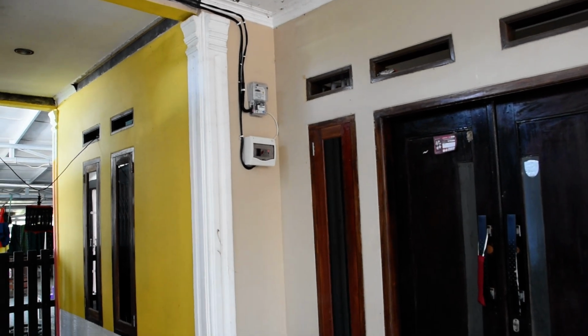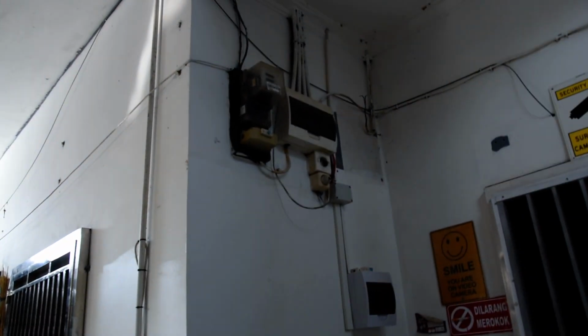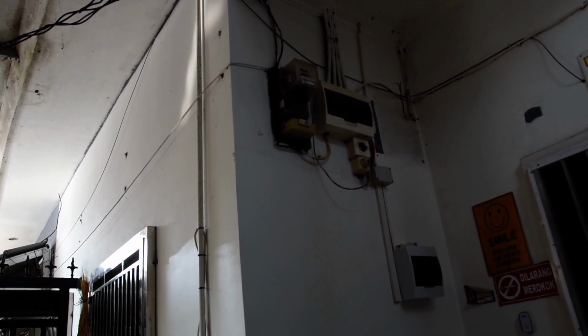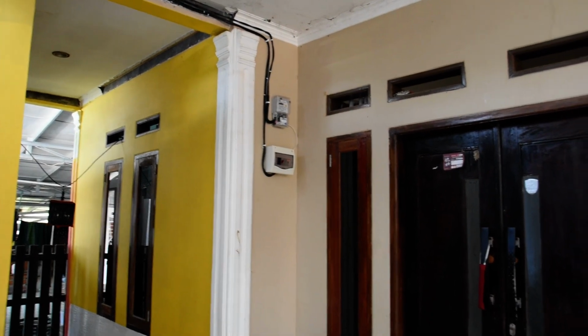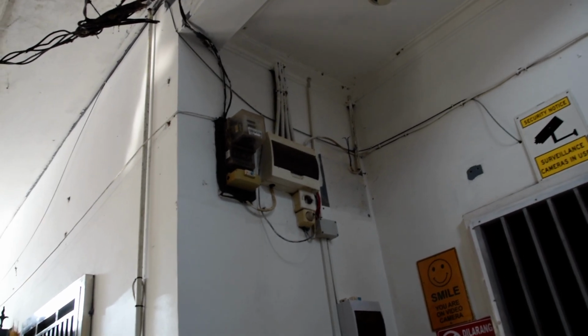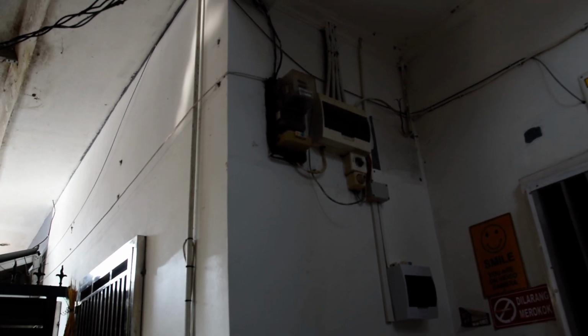So a major driver in getting Lizu's house on the Publik Listrik Network, with just backup from the off-grid network, was to reduce the overnight load on this old switchboard with the house, thinking that might reduce the chances of tripping that breaker. The last event where it tripped 4 times overnight was after we got that new meter over here at Lizu's house. So I really don't understand. At this point, the only things on that old switchboard are the lights, the 4 of the air conditioners along the south side of the house, of which only 2 are usually in use at one time, and pumps.